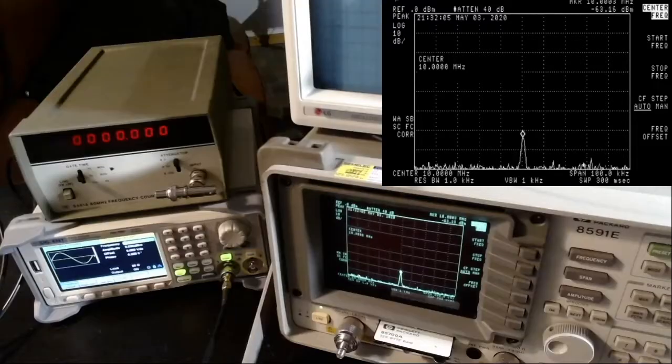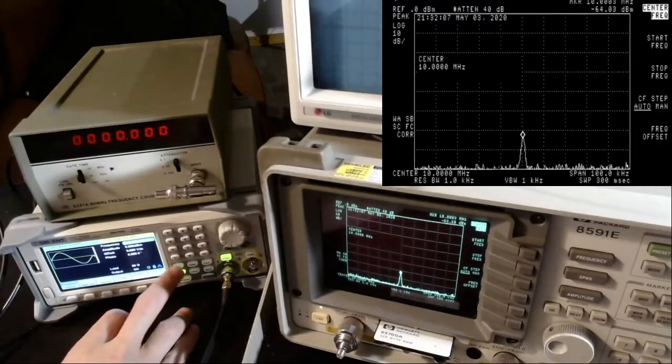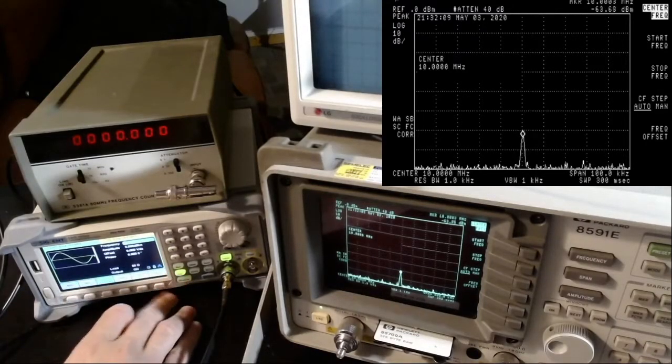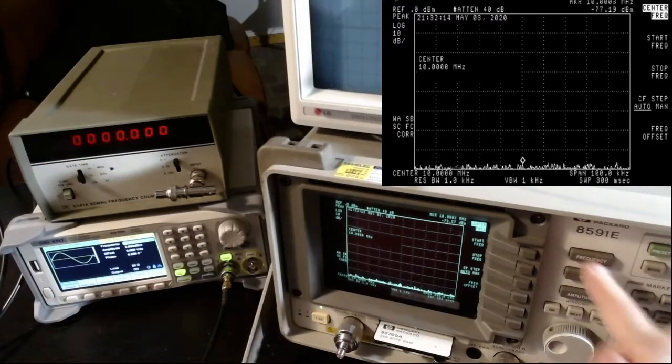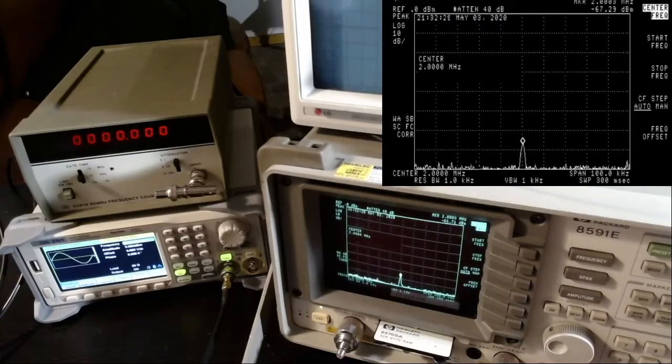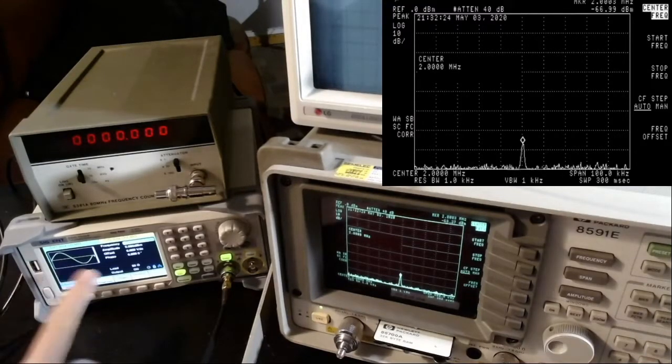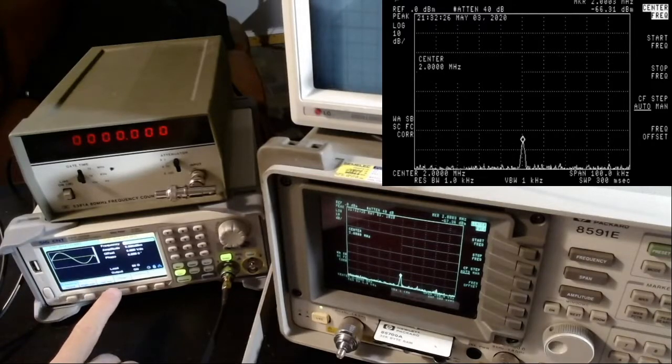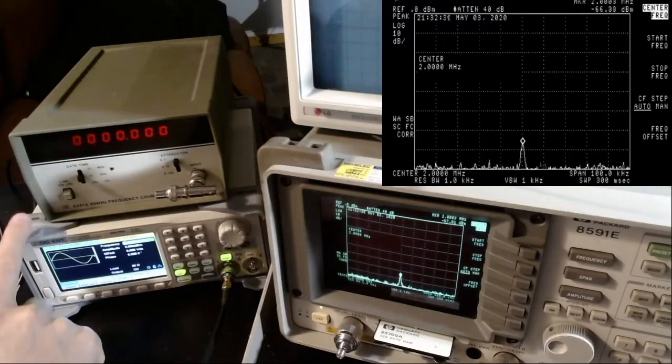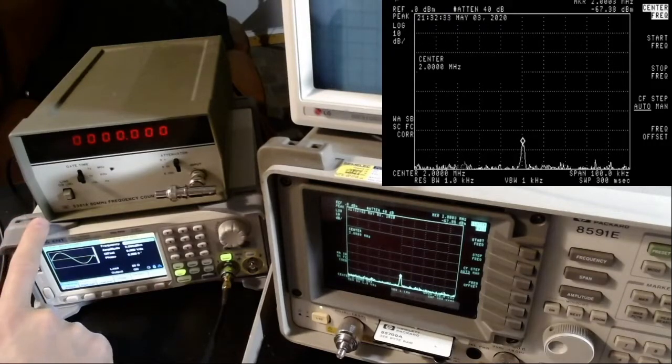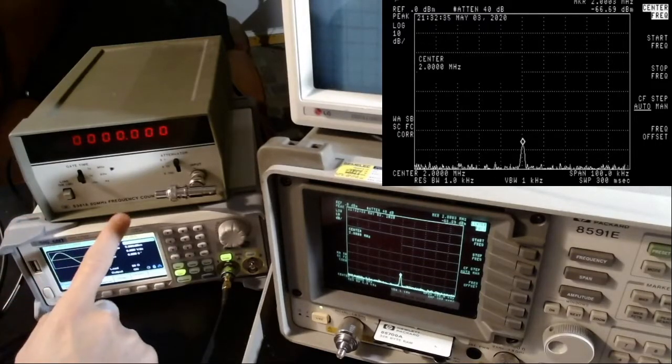Let me try 1 megahertz. The first harmonics is at 2 megahertz. There it is at minus 66. Again, the unit is in fact better than specification, which is great. This is not surprising. I was a bit surprised when I found out in the previous video that this unit did not meet the specifications, because when it is sold it comes with a certificate of calibration.